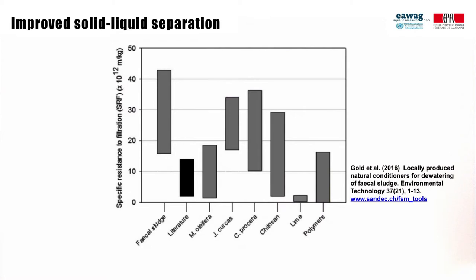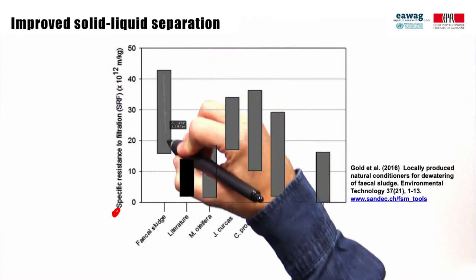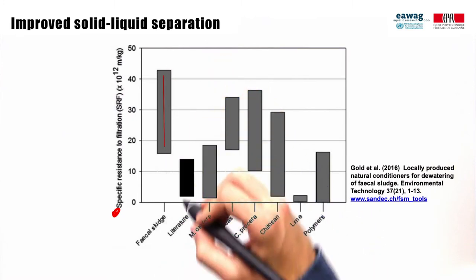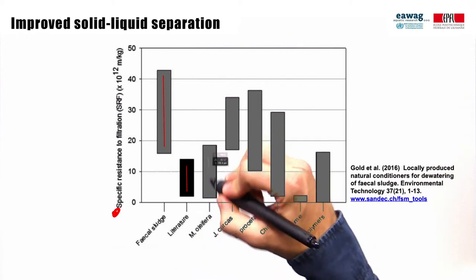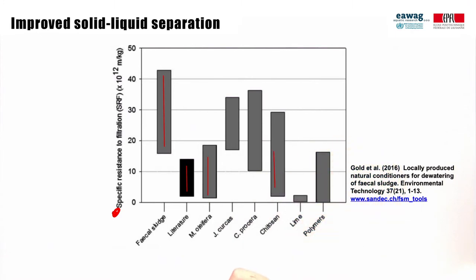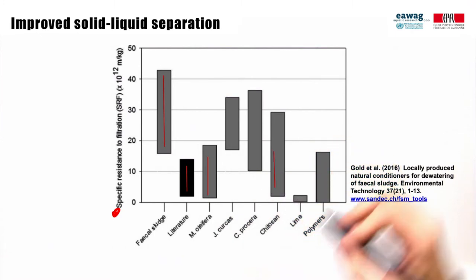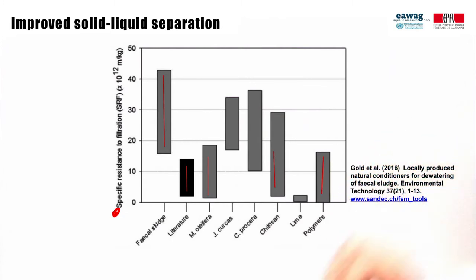This graph shows the results of specific resistance to filtration. Specific resistance to filtration is another metric to measure the dewatering rate — a low resistance to filtration means fast dewatering. From this graph we can draw two conclusions. Firstly, the dewatering rate of unconditioned fecal sludge is significantly lower than those compared to wastewater and water treatment sludge results from the literature. Secondly, Moringa oleifera and Chitosan were as effective at increasing dewatering as commercial polymers used in wastewater sludge treatment.